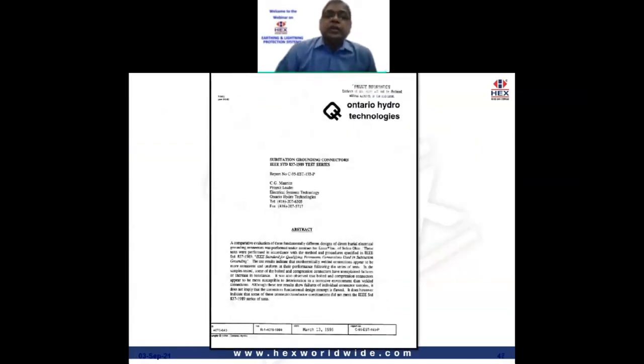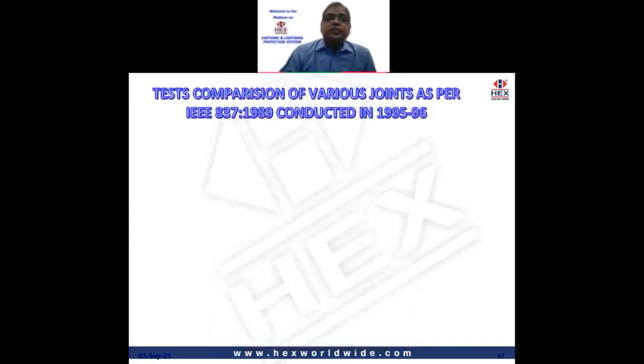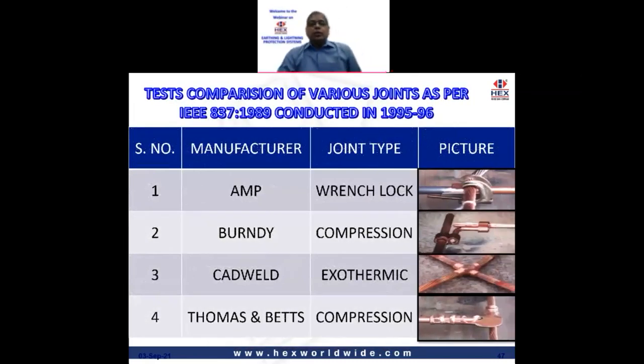Now, this is a study that was done at Ontario Hydro Technologies from 1995 to 1996 on different types of grounding connections as per the IEEE 837 standard. They compared mechanical, compression and exothermic welded connectors. Now, these were the results of this test. These are the manufacturer, the joint type, and the pictures of the products. This is in their report.